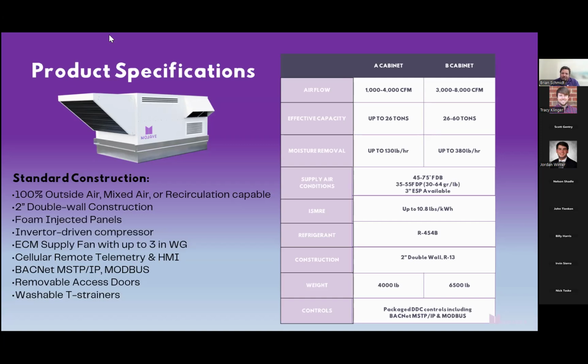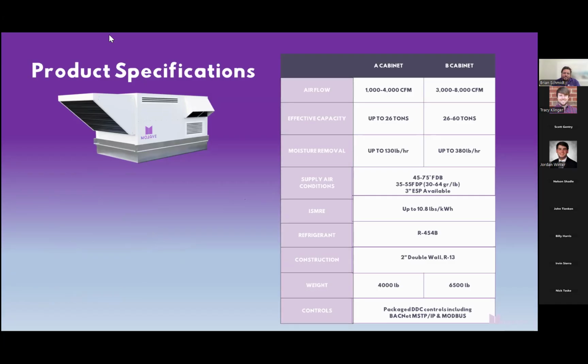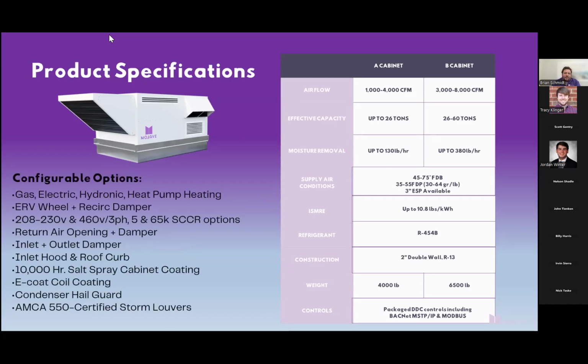ISMRE is up to 10.8. And weight, again, might be a little bit higher than you're accustomed to. Obviously, this has some variable components or factors as well, but we are a little bit heavier than your traditional DX system. And some of the configurable features, as I mentioned before: the winter heating module can be gas, electric, hydronic, or heat pump. We do have the capability to have an ERV if you need it or if you'd like it. And then we have your typical return air openings and dampers, and inlet openings and dampers.